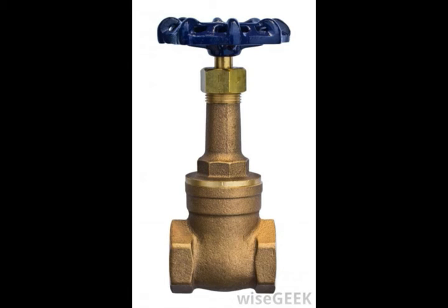By allowing material to flow unchecked through the open block valve, certain common valve types are excluded from the group. For instance, a globe valve typically has two chambers, and the material flows through them. Even when open, the flowing substances are disrupted by the process of moving from one chamber to another. The second restriction removes check valves and other one-way valves from the list since the material is only blocked from one direction. This definition is more of a rule of thumb than an actual specification.